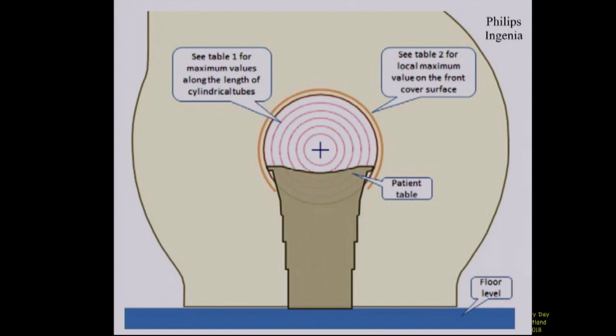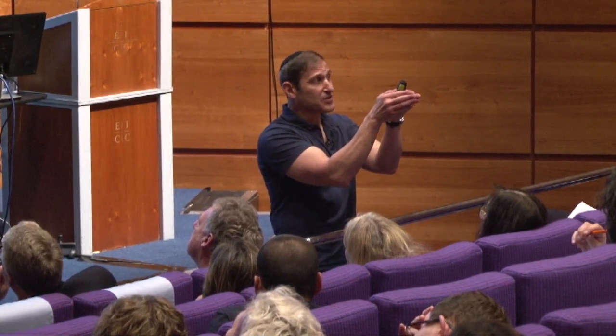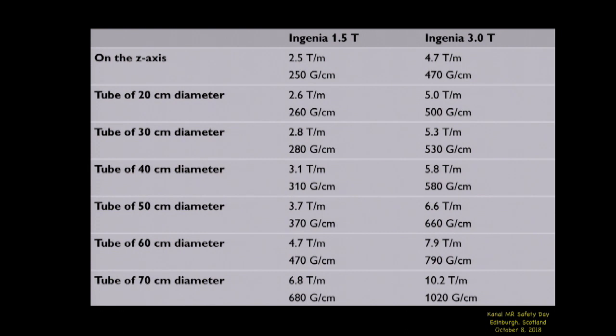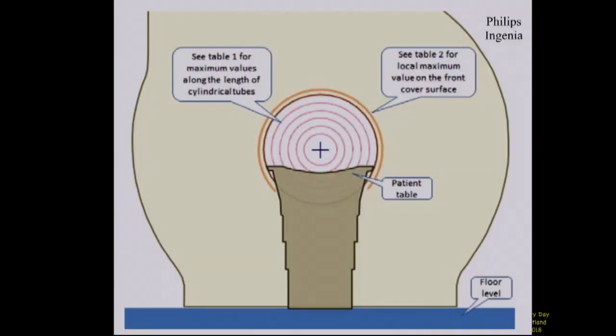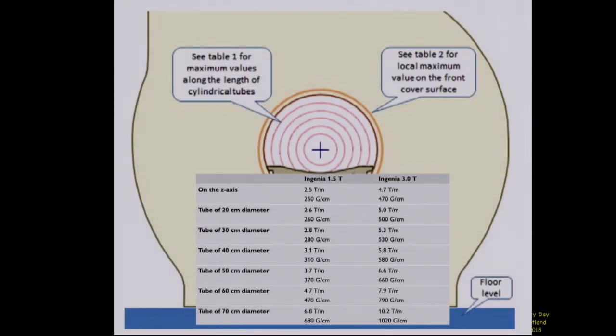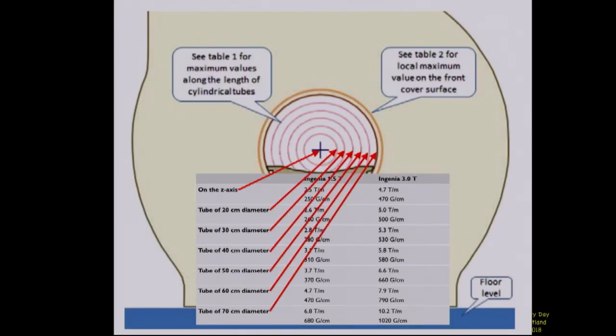Looking down the bore for yet another MR scanner, I'm trying to remind you it's a three-dimensional field, which means that as you look down the bore, in the dead center of that magnet, the field strength and the dBdx is noticeably different than as you get further and further out radially towards the walls. Does that make sense? Of course, you're standing next to the flashlight, the hardware. And so out here, they give you these numbers for the different diameters. So I just took this table from that company and this picture from that company, and I put them both on the same page to have you understand this is what they're talking about.